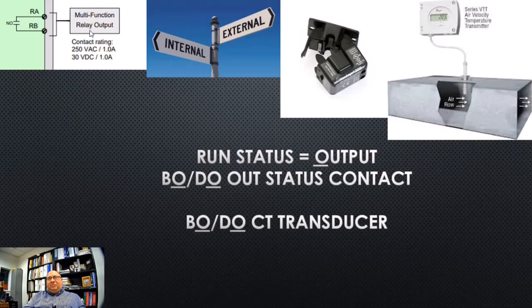So some of the external devices that we'll add to a system is maybe a little CT called the Hawkeye. We're going to put that around the motor windings, or the leaving wires going to the motor, that will sense amperage, okay? And it will let us know if the motor is running. Something even more effective would be actually a velocity transmitter, all right, that will know that there's actually static in the ductwork. Because what could happen is you could start the VFD. If it's a fan powered VFD, it could get through the belt, or the belt could be damaged. We still measure status that it's running through the output of the drive, but yet there's no rise in static air pressure.